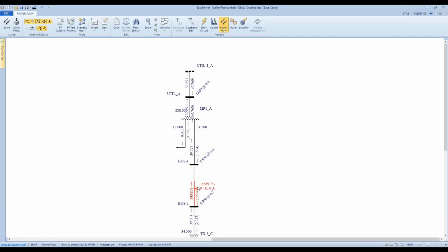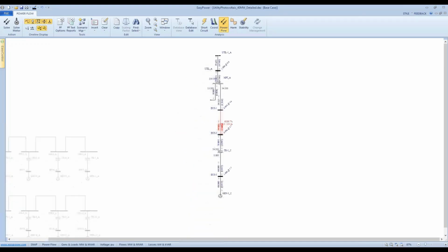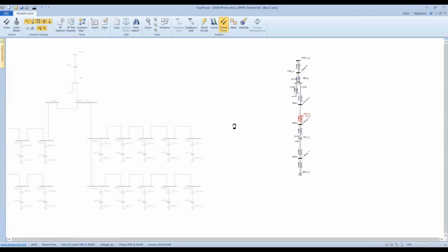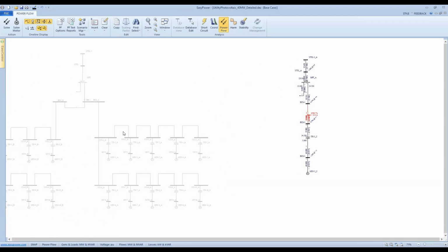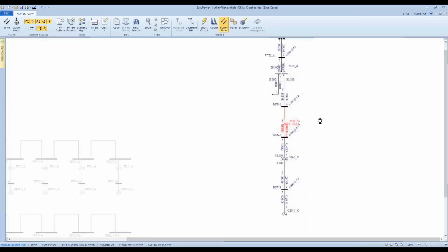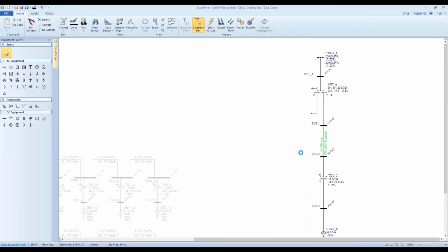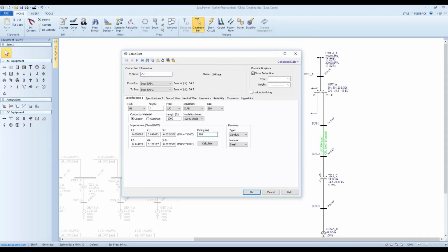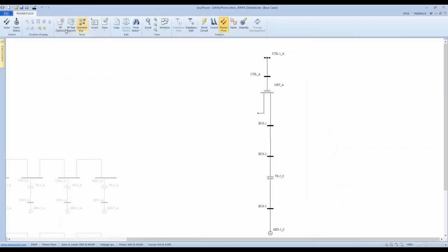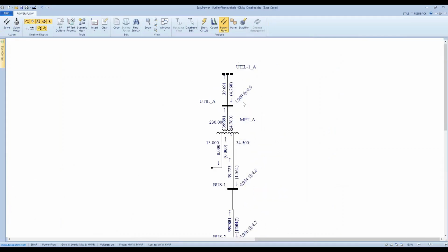Please forgive me about the collector system ampere rating. The ampere rating of the collector system equivalent is meaningless because it's an equivalent circuit. It does not have any rating at all. It's not practical. The rating of each cable is already predetermined by your design. So when it comes to the equivalent cable, it really doesn't matter. But for the sake of clarity, I will just set it as 99999 to avoid any overload. Fine, it is okay. Solve the power flow, solve, okay.